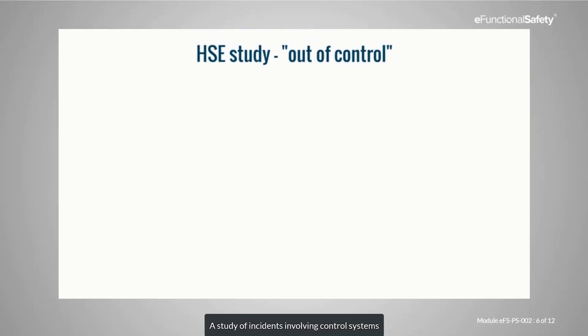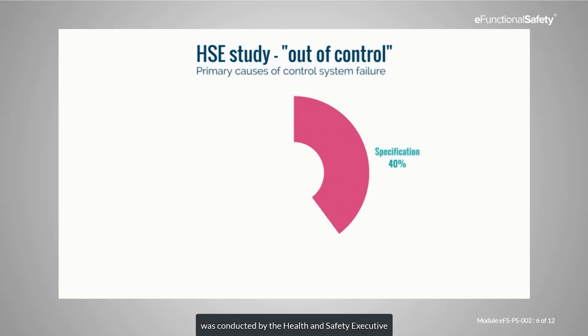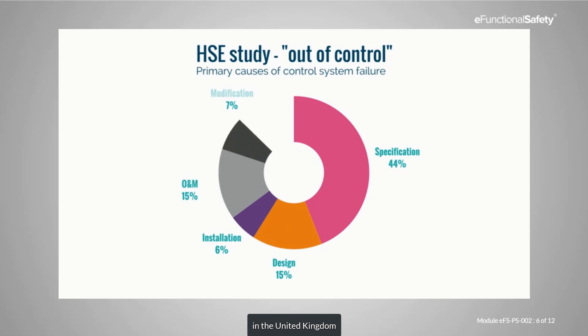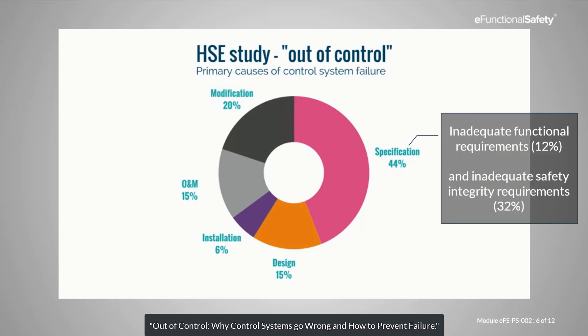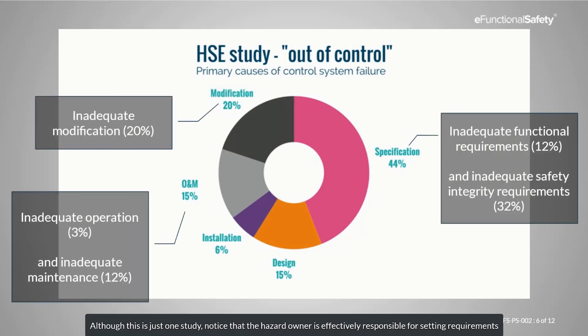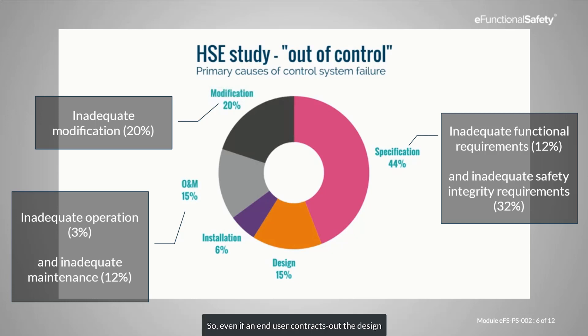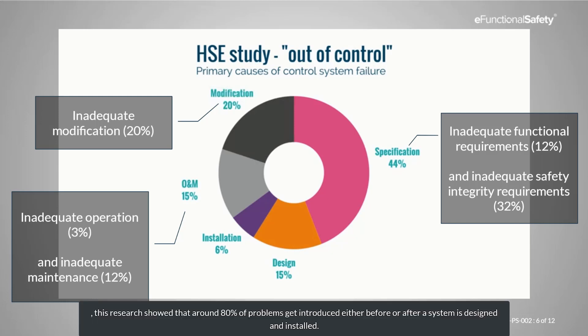A study of incidents involving control systems was conducted by the Health and Safety Executive in the United Kingdom, with the first results published in the book Out of Control: Why Control Systems Go Wrong and How to Prevent Failure. Although this is just one study, notice that the hazard owner is effectively responsible for setting requirements, as well as operating, maintaining and modifying an SIS after it has been placed into service. So even if an end user contracts out the design, this research shows that over 80% of problems get introduced either before or after a system is designed and installed.